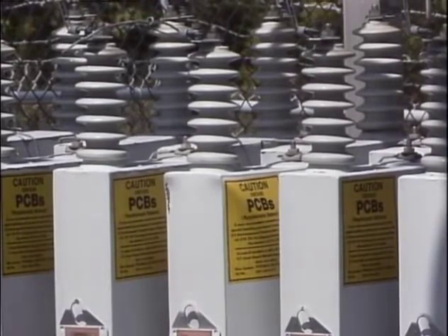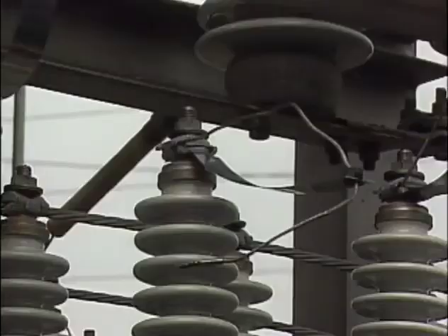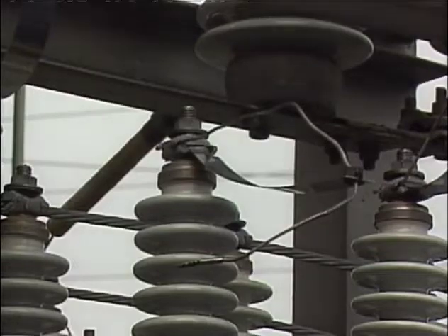When it's obvious that a failed capacitor caused a fuse to blow, as is the case here, both the fuse and the capacitor are replaced. When a fuse is blown, but the capacitor appears to be normal, it may be necessary to test the capacitor to determine if it is good or not. We'll look at testing capacitors later in this program.